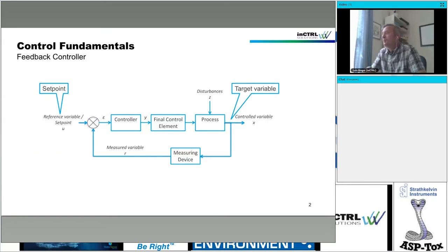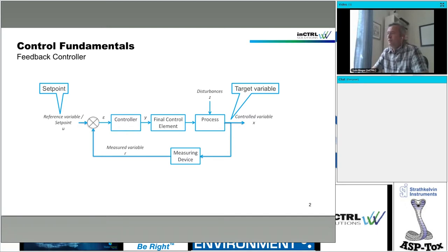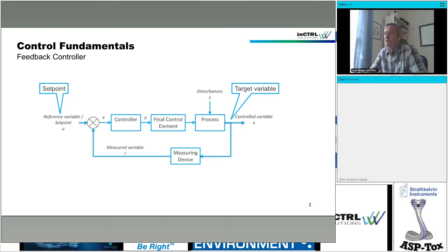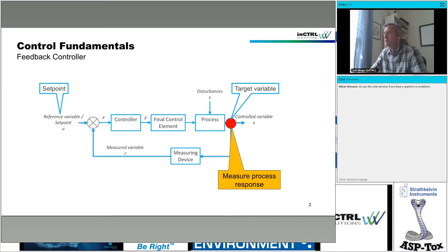So let's jump right into control fundamentals. There are two basic principles for control loops. The classic one is feedback control, typically implemented in the form of a PID controller. The feedback control is that you want to control a certain variable and you define a set point, and then you want to make sure that your control variable is around the set point. The special thing here is that you measure the process response, so you don't fully have to understand what's going on inside the process because you measure the control variable coming out.